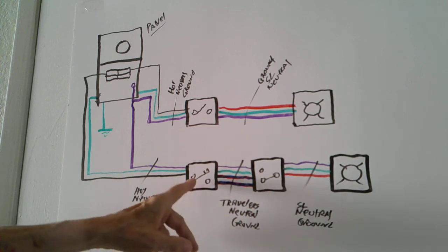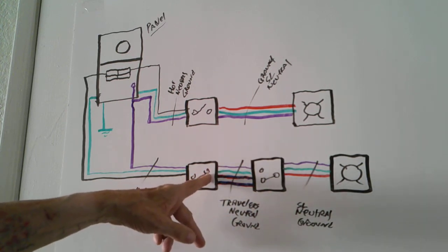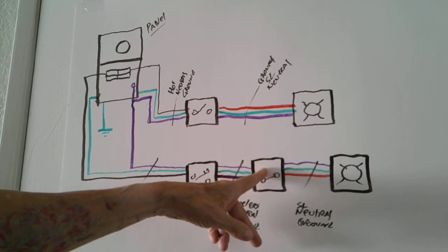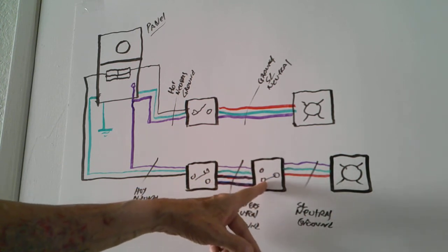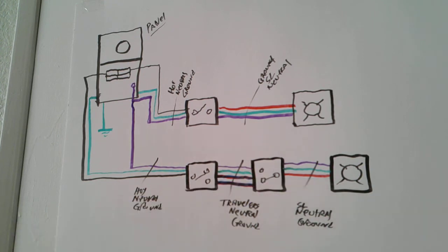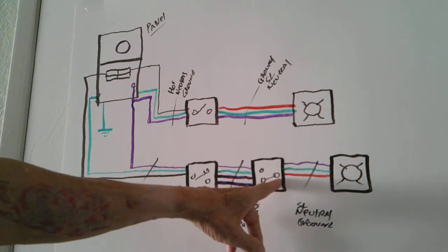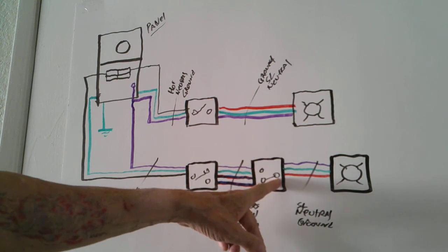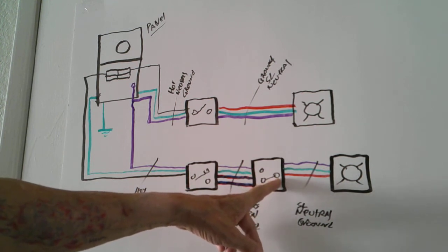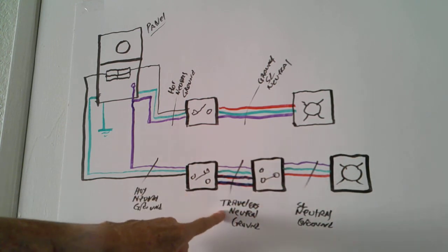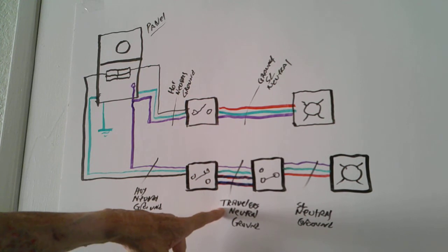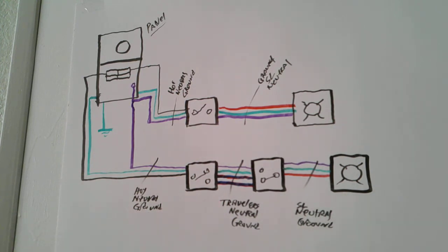Okay, so when this switch is turned on in one position, you should have a hot line here going to neutral or ground, or a hot line here going to neutral or ground. And that would be either one of the two brass screws on your switch. Or what you can do is you can go to the black screw on the second three-way switch, to the neutral or the ground, and see if you have power. In the event that you don't have power and it's not wired correctly, that means that these travelers here are not wired correctly. Oftentimes people have a problem with wiring the travelers on three-way switches.